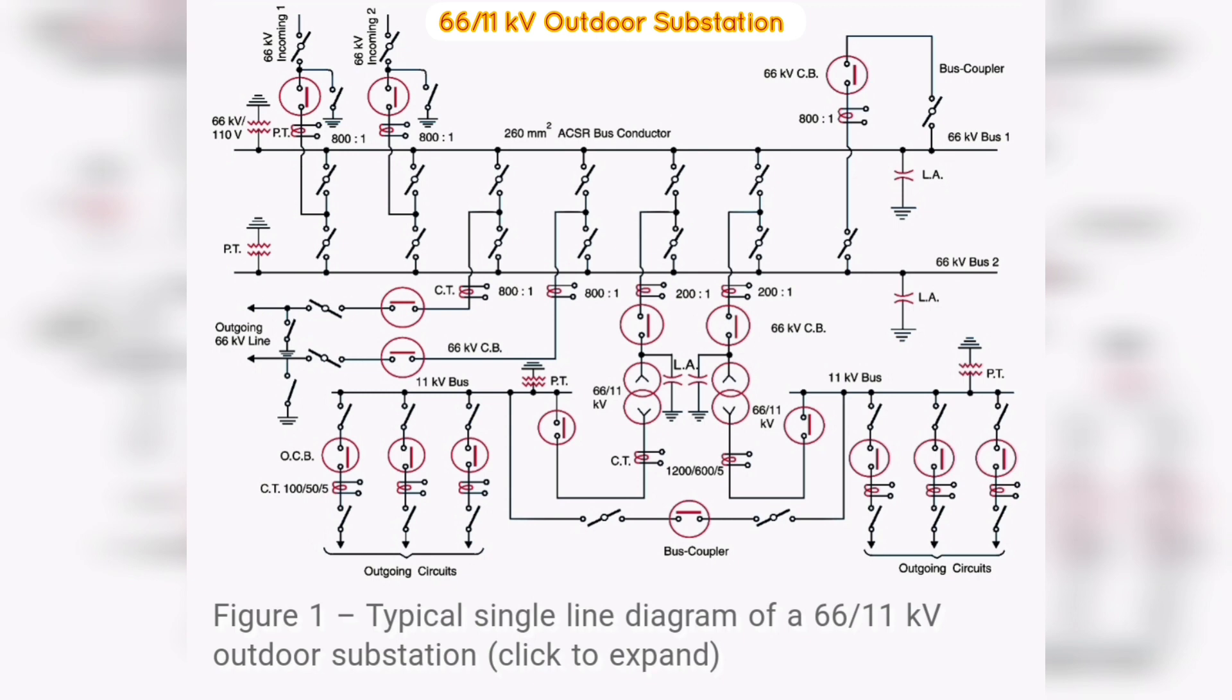The incoming lines can be connected to either bus bar with the help of a bus coupler, which consists of a circuit breaker and isolators. The advantage of the double bus bar system is that if repair is to be carried on one bus bar, the supply need not be interrupted as the entire load can be transferred to the other bus.